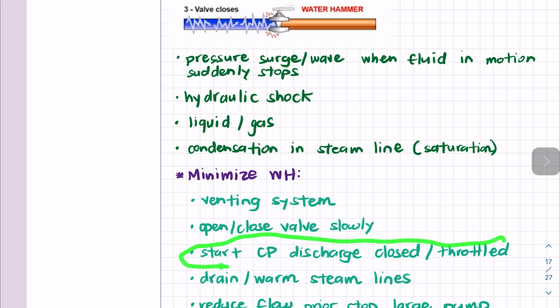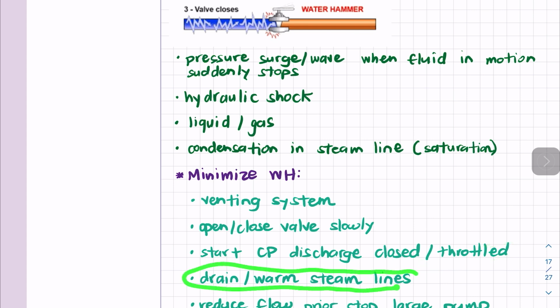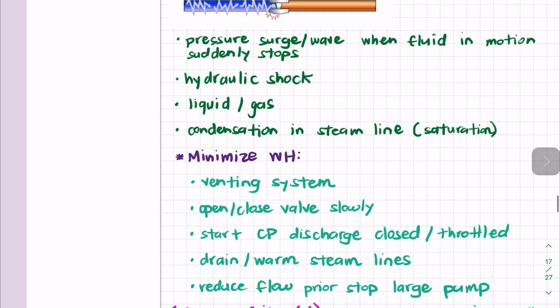Also, we can start a centrifugal pump discharge either closed or throttled. Another important thing for gas lines is to drain or warm the steam lines, which is very important because of the difference in temperature. If there's a difference in temperature, that can also cause a pressure spike.